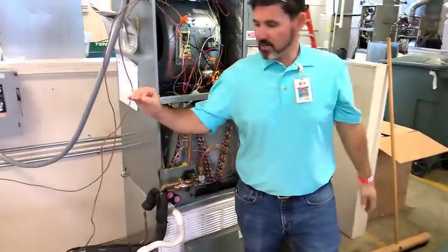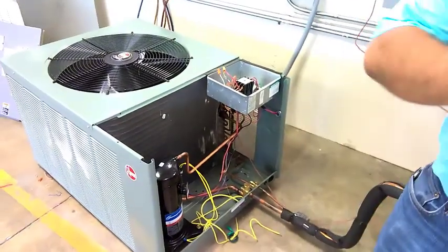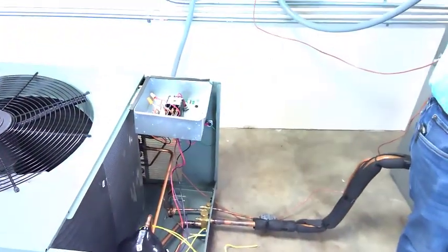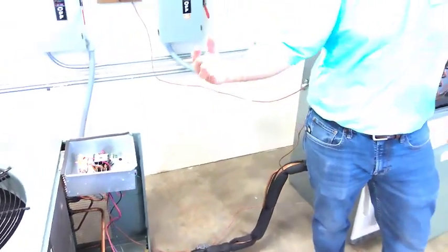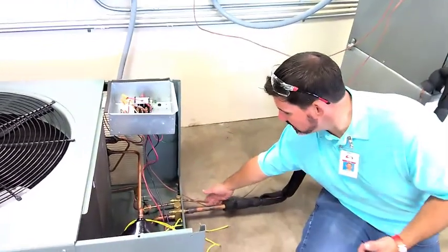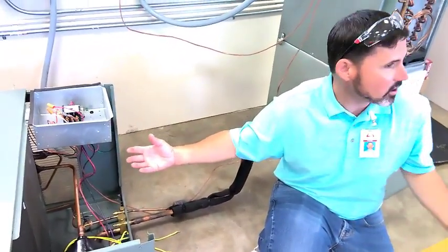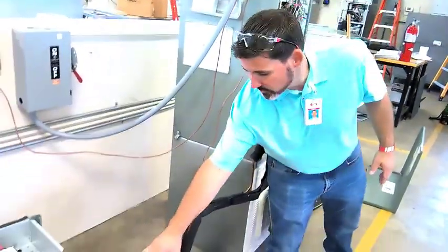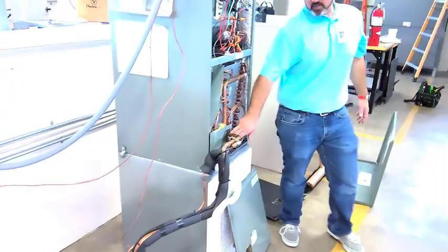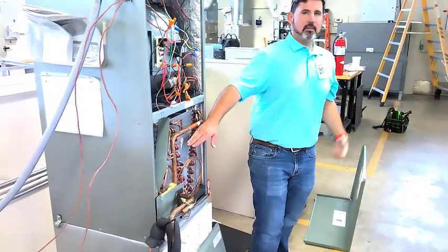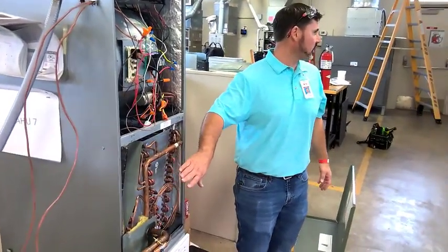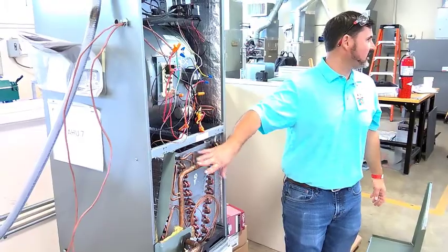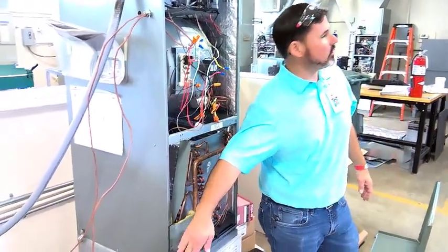All right. So just to recap our components, we have a compressor. I leave the compressor on my discharge line as a hot, high pressure vapor. I go into the condenser where I condense it into a liquid. So I leave as a warm, high pressure liquid. The pressure here and the pressure here is pretty much going to be the same. My discharge and my liquid line should have approximately the same pressure, within 1 or 2 psi, hopefully. All right, so my high side pressure is all one pressure, but I went from a vapor to a warm, high pressure liquid. I hit a metering device, which restricts it. As soon as it comes out of that metering device, it starts turning into a cold or cool, low pressure liquid that's vaporizing. All right, so I've got cool liquid flashing off into a gas as I go through here. When I leave on my suction line, I should be 100% vapor.